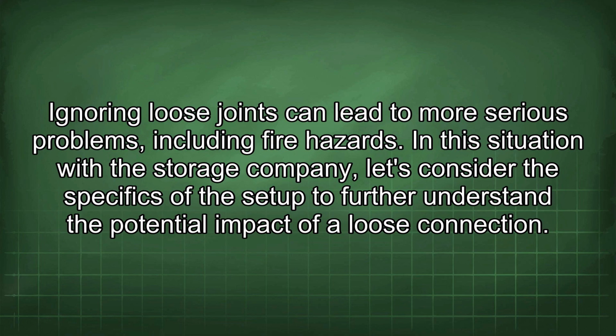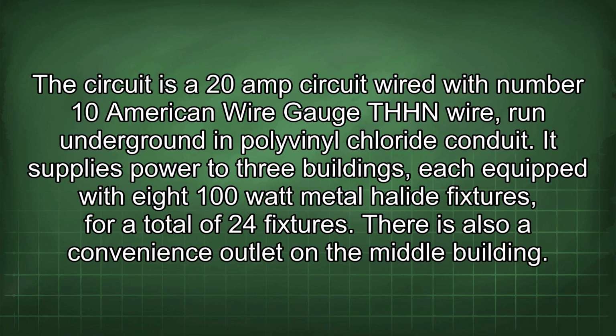In this situation with the storage company, let's consider the specifics of the setup to further understand the potential impact of a loose connection. The circuit is a 20 amp circuit wired with number 10 American wire gauge THHN wire, run underground in polyvinyl chloride conduit. It supplies power to 3 buildings, each equipped with 8 100-watt metal halide fixtures for a total of 24 fixtures. There is also a convenience outlet on the middle building.